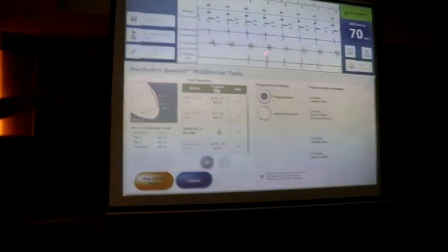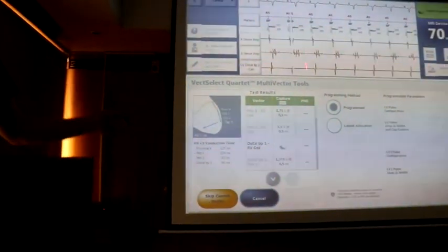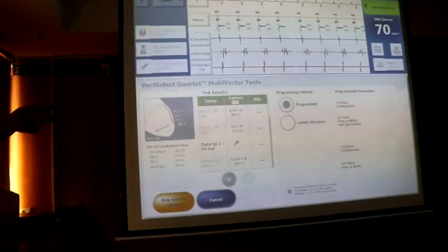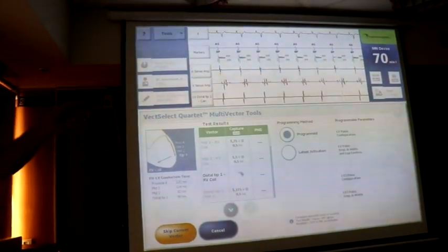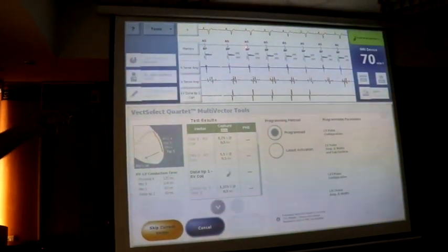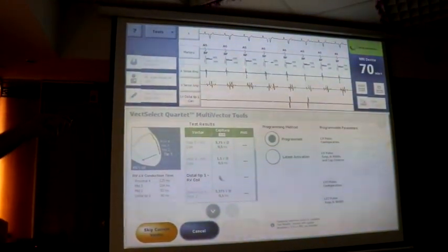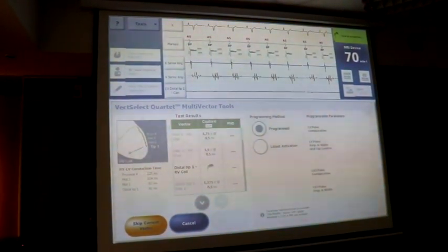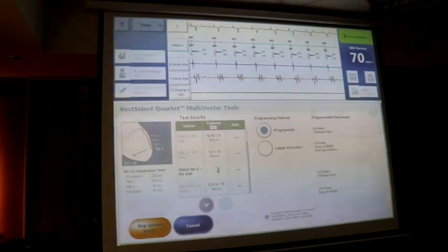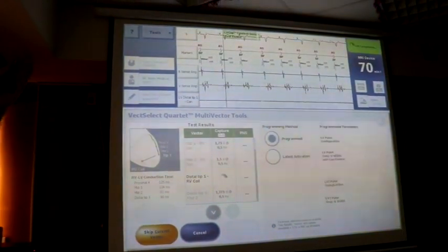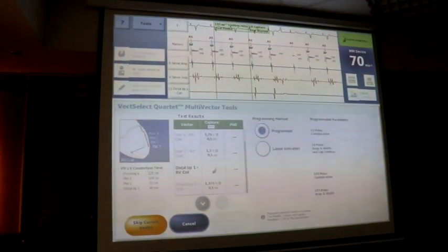So it's running the threshold, as I said, but we don't even look at it, right? It delivers LV pacing and then an RV backup pulse. LV pace, RV backup pulse. So it says bi-V pacing, right? But actually, first thing is an LV pulse, and then it brings in an RV backup pulse about 90 milliseconds after it. Okay, so if the LV electrode doesn't capture at all, you've got a backup in the RV.